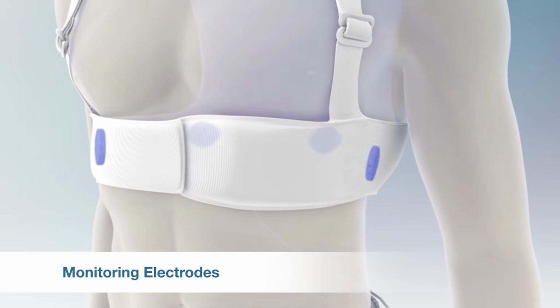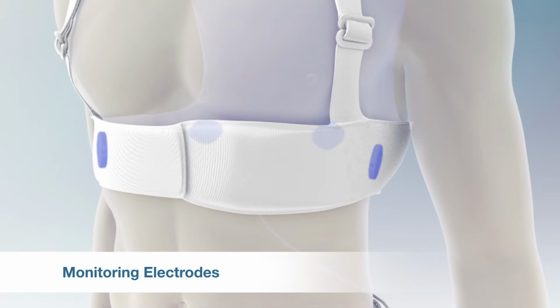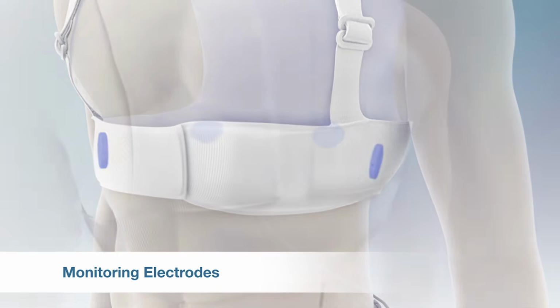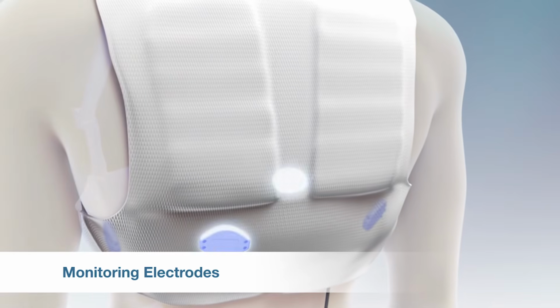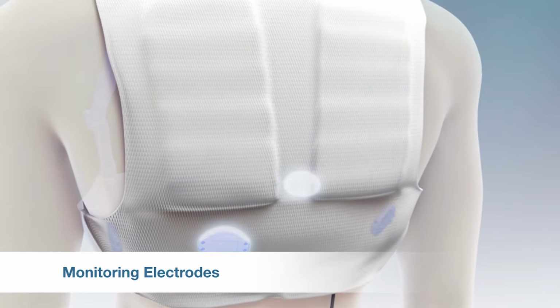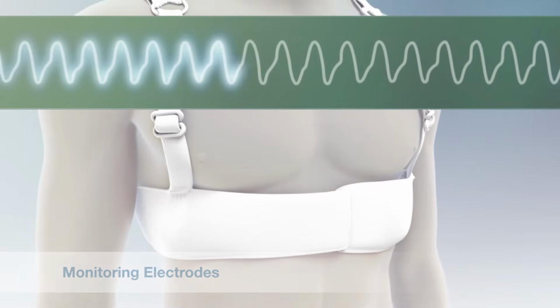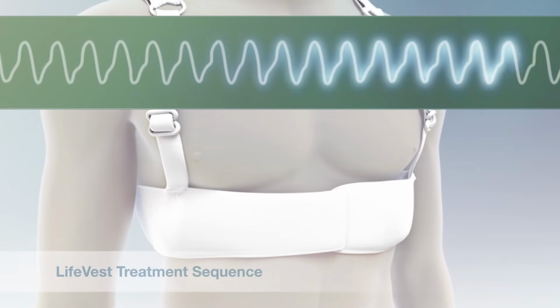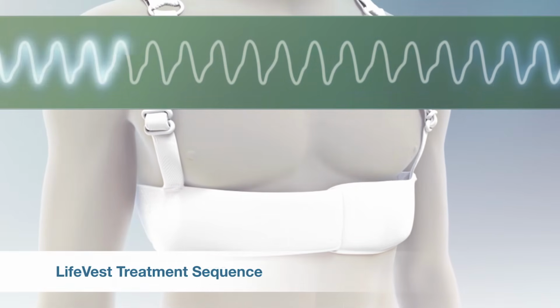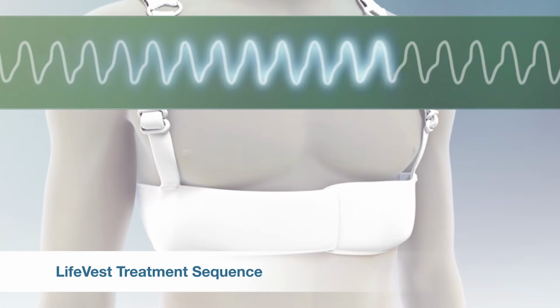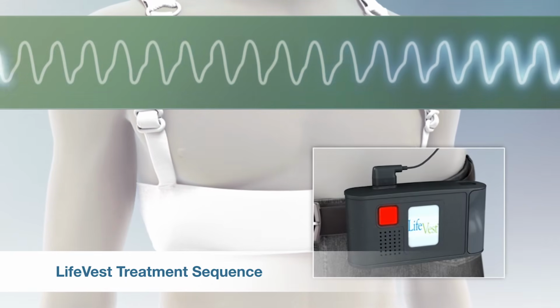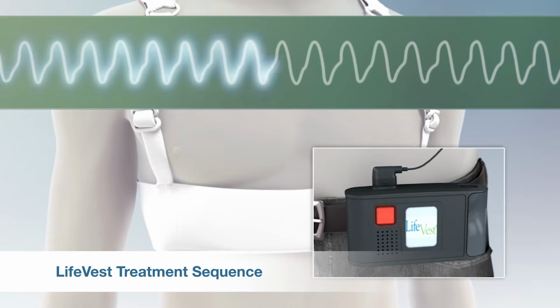The LifeVest system uses 4 ECG electrodes around the patient's body. One pair of electrodes provides a side-to-side channel of the ECG signal, and the other pair of electrodes provides a front-to-back channel. When a treatable ventricular arrhythmia is detected, LifeVest initiates a sequence of alerts and voice prompts to warn the patient and bystanders of a possible treatment shock.